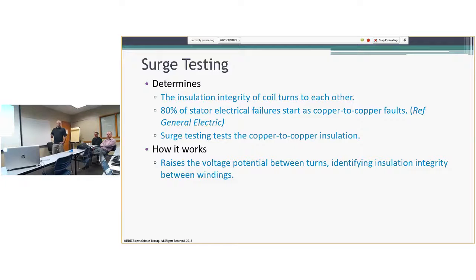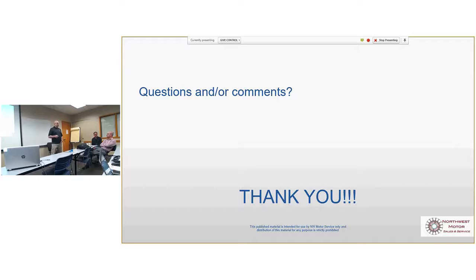Any more questions? Do you test rotor bars or anything like that? Yeah, so the online test equipment that we were talking about tests rotor bars. We need to have at least 30% load on the motor, and what I do is take the nameplate information off the motor and enter it into the test before we start, and that's how the test equipment knows what we're looking at. Based on that, we know the frequency of interest of that particular rotor bar. So we're looking for a certain spike at that frequency of interest, and if the amplitude of it is too high, we know we could possibly have a rotor issue.